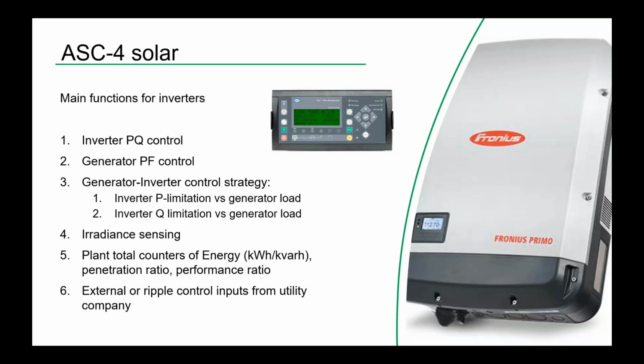Control strategies also when we have generators and inverters working together. For a little bit specialized applications, we can limit the power of the inverter in order to produce more reactive power. This is if you have comparably small generators compared with the inverters, and some control strategies there. Irradiance sensing is important, at least in some areas. This depends on where you are in the world, but you would need them to calculate the curtailment. Counters are actually also available for all the production, whether it's PV, generator, mains, and of course the curtailment. And then you can control from the utility company side if you have a box which accepts ripple control, or you bring in external control.